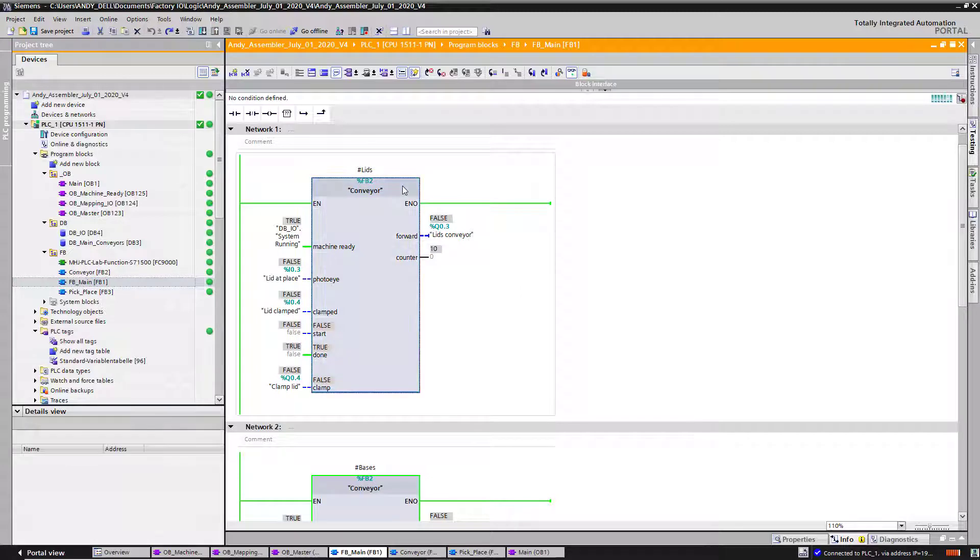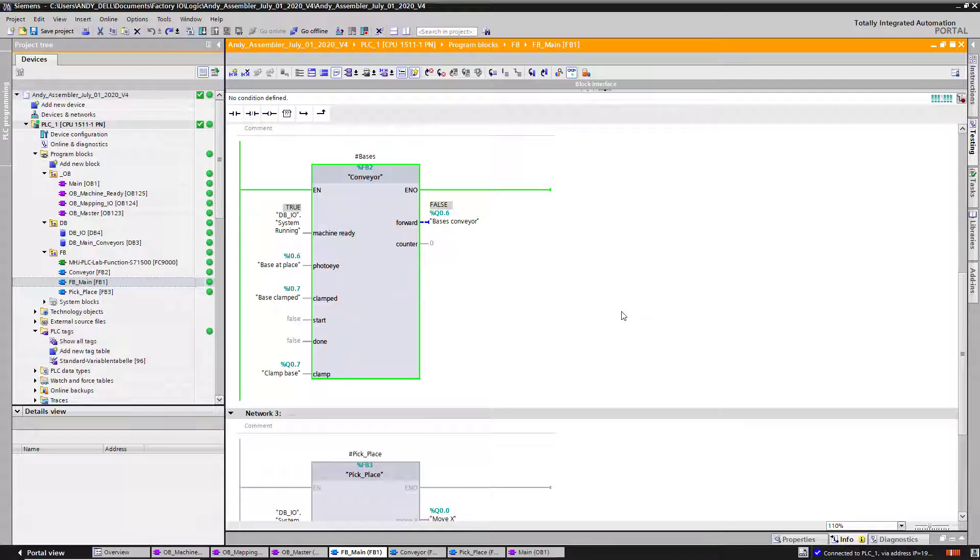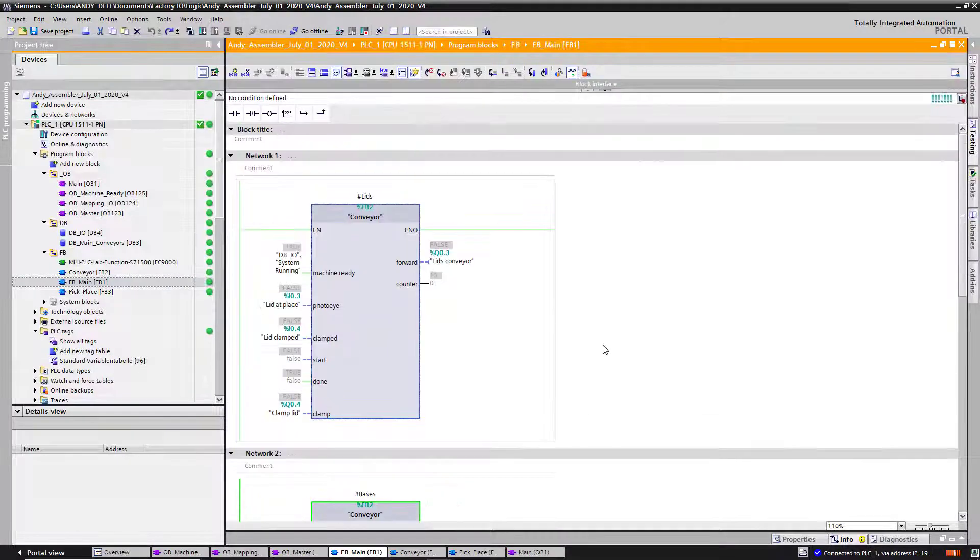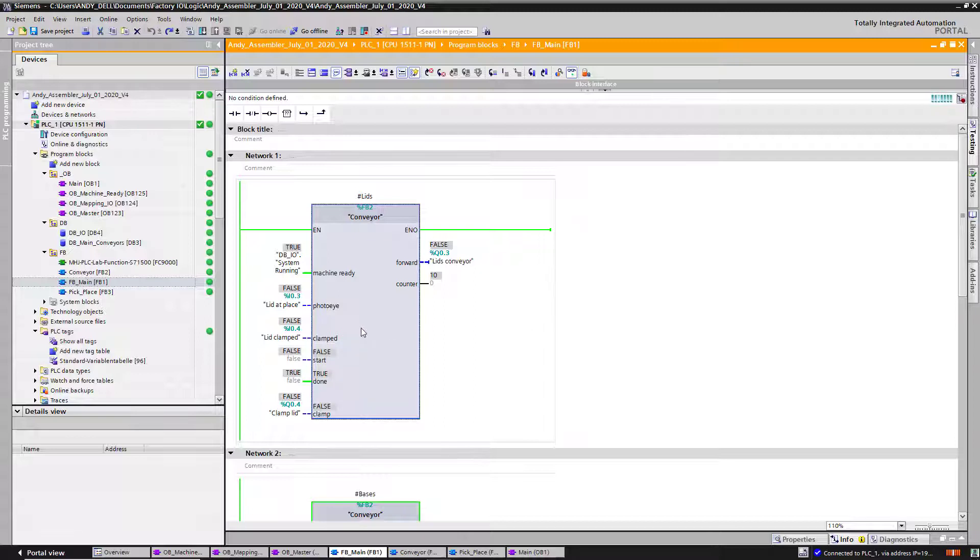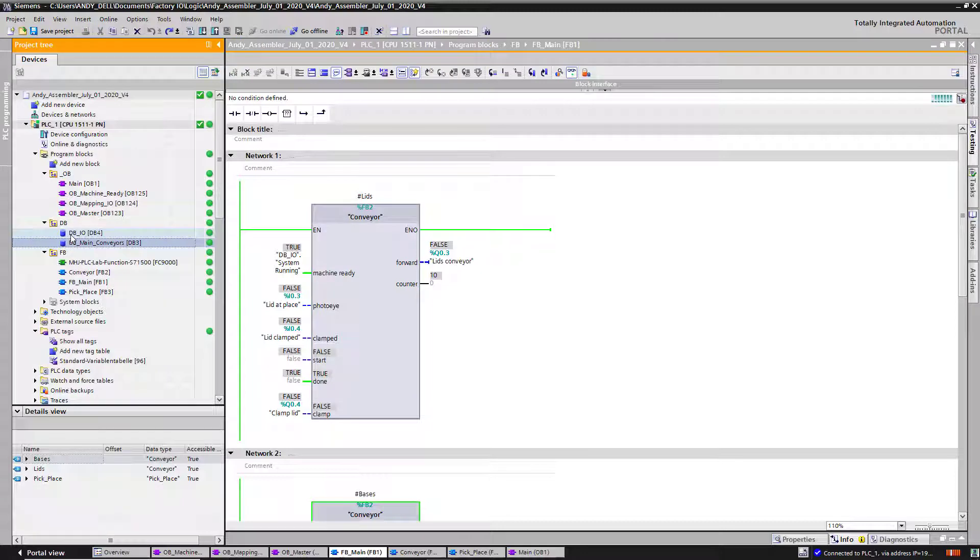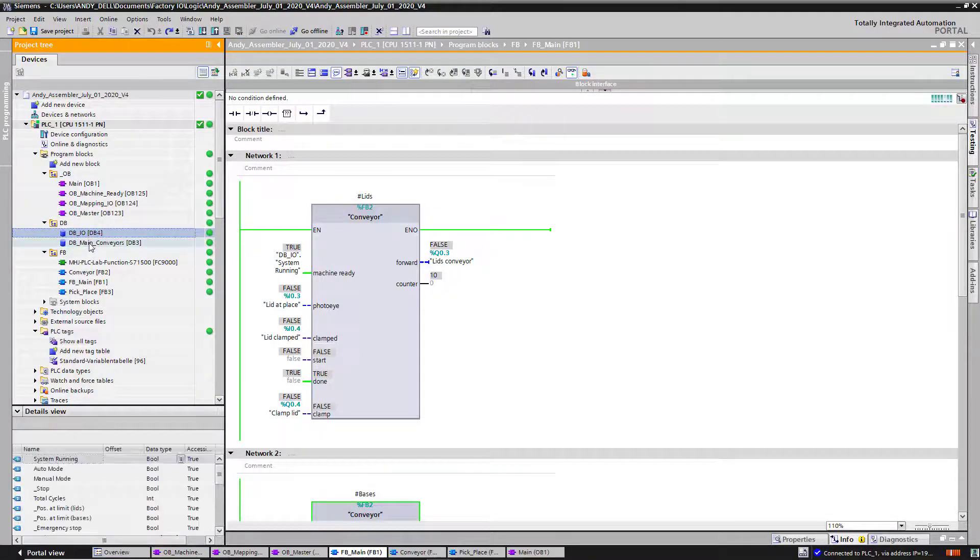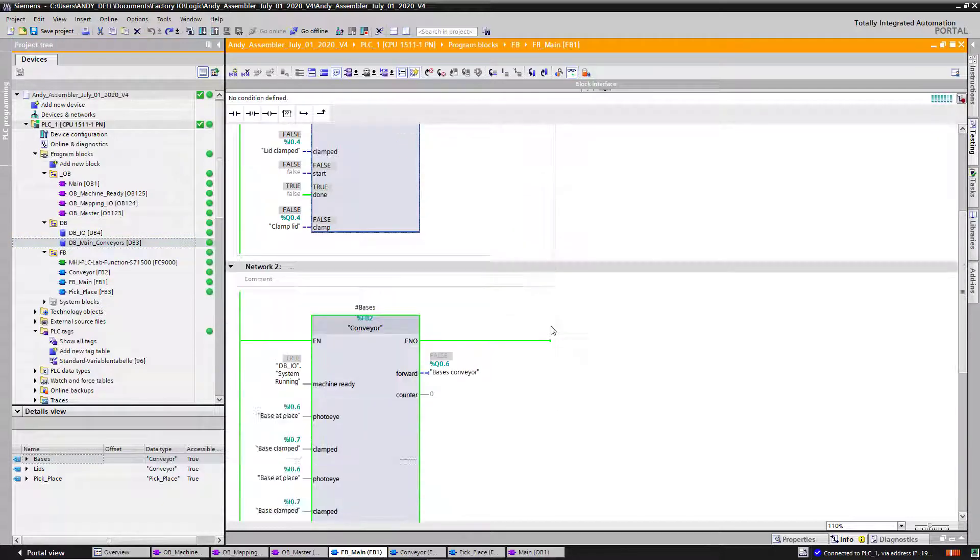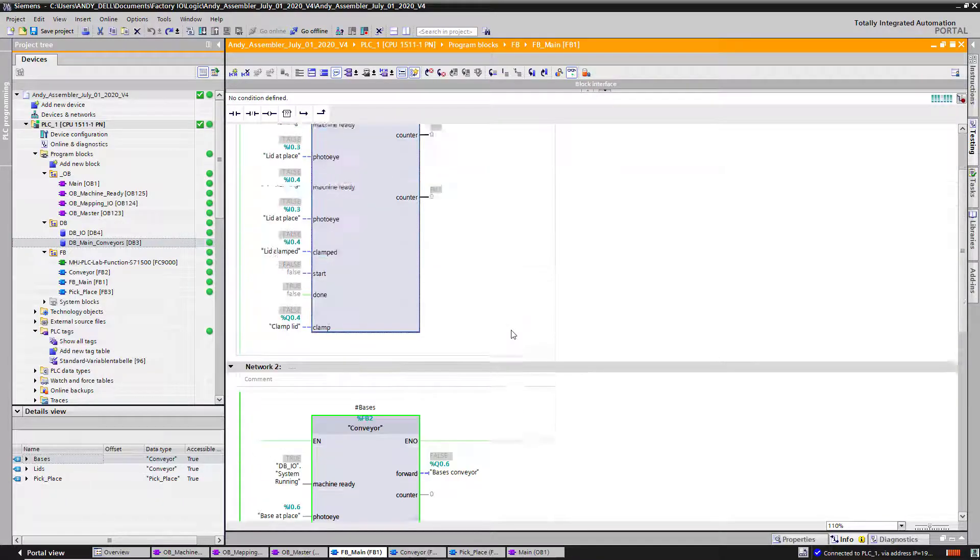I created a function block main and then inserted all the other function blocks inside main. This way I can choose multi-instance for my function blocks instead of single instance. That way I don't create so many data blocks. Right now as you can see, I only have one data block, which is my main data block that controls these three function blocks.